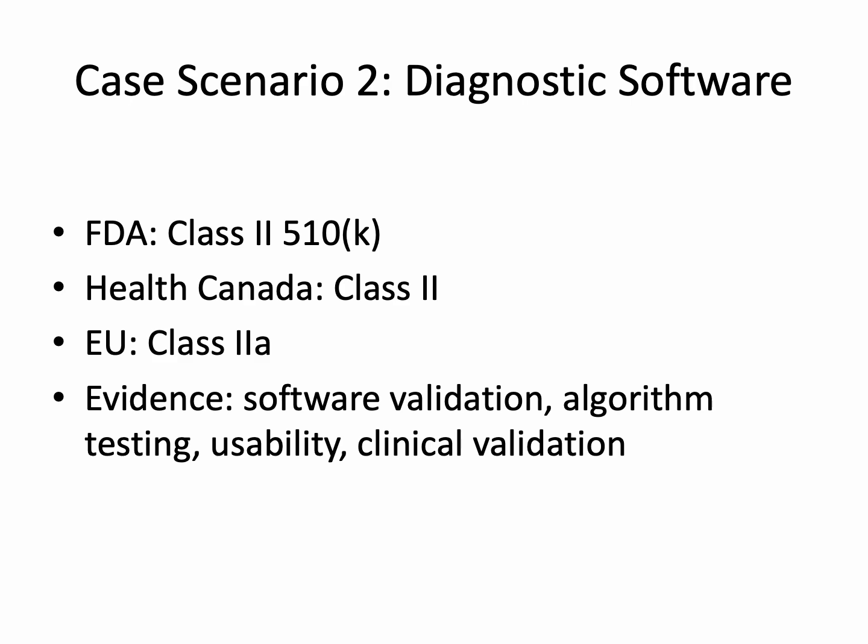Evidence includes software validation, algorithm performance testing, usability studies, clinical validation using retrospective datasets, comparison to human reader performance, and risk analysis focusing on false positives/negatives. Software devices require both technical and clinical evidence to demonstrate safety and effectiveness in target populations.